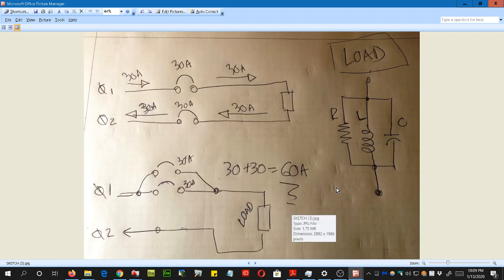Okay, here's the example I showed where you got the 2 breakers, you know, the 2 pole. 30 amps flows through the breaker, through the load, and then back out again. There's no 60 there. If you had some kind of jumper here where these are in parallel, where half the current goes through this 30 amp breaker and half goes through the other 30 amp breaker, then I could maybe get 60, but that's not something you're going to see. So, trying to help the person who thought it was 60 amps.